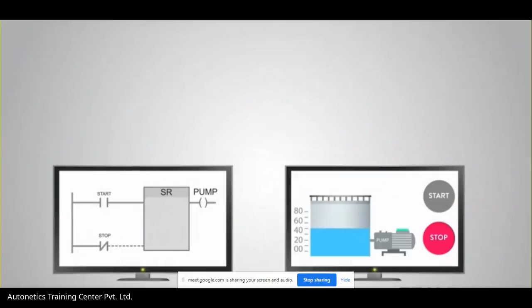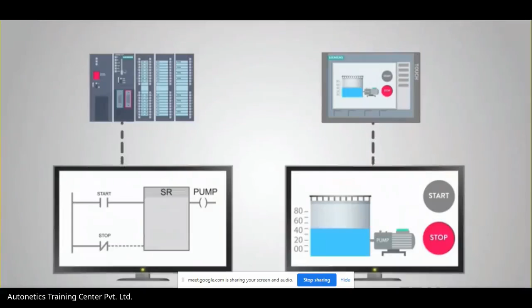But it's not as easy as just placing a button on the screen or a tank with the level on the screen. In programming the HMI, each indicator and button has to be programmed to a specific input or output address of the PLC. This brings up another point.